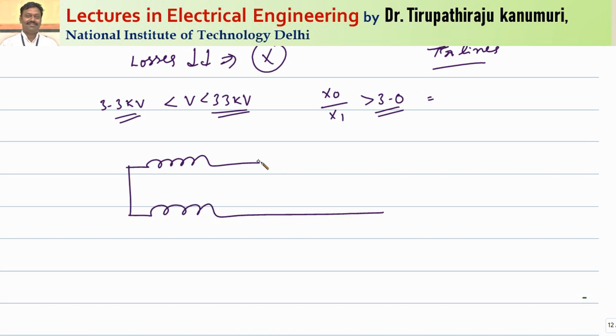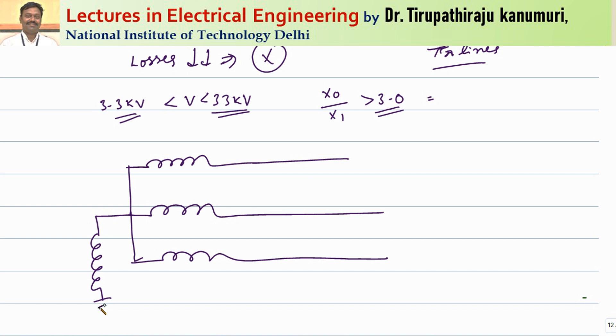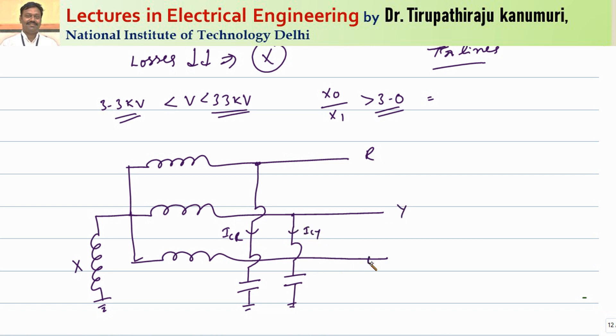These are the three phases connected through a reactor. The value of the reactor is decided accordingly to limit the fault current, since a minimum value of fault current is required so that switchgear and equipment can detect the fault. The current passing through the capacitor in the R phase is ICR, and in the Y phase is ICY. Assuming the fault has occurred, the fault current passes, and the sum of these two capacitor currents gives ICF — the capacitor current passing during the fault — all returning through the neutral wire.